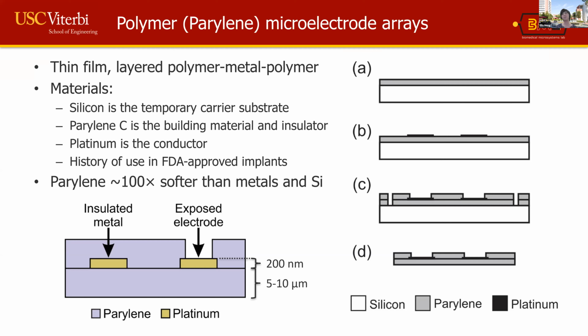And the reason for choosing these materials, it's sort of a safe approach, and that ultimately the goal is to be able to develop implants that can be used clinically. And so we've chosen to use materials that are present in other FDA-approved implants as a lower risk approach to attaining that one day. The construction, here's a cutaway view, a cross-sectional view of what a typical device might look like along an electrode site as well as along a trace. We use typically 5 to 10 microns of parylene per layer, and the electrodes are about 200 nanometers. So that gives you an idea of scale, and the width and the specific geometry will vary based on the application. And I'll kind of show you what we can do with these devices.